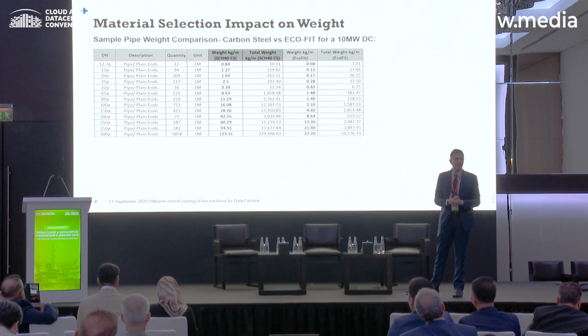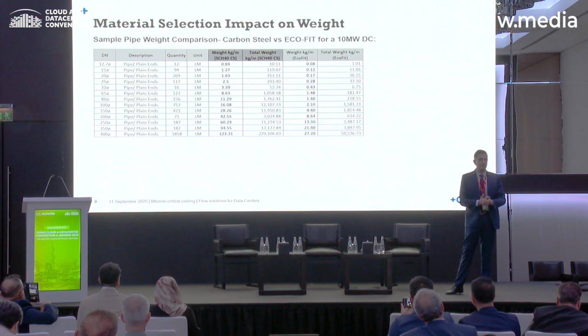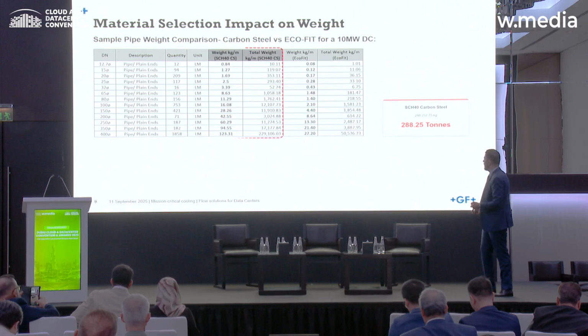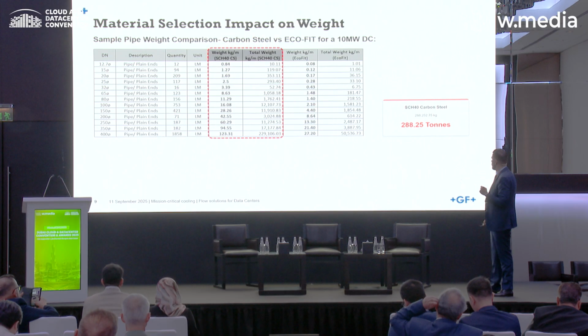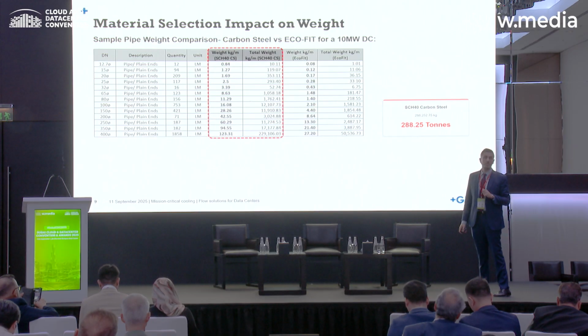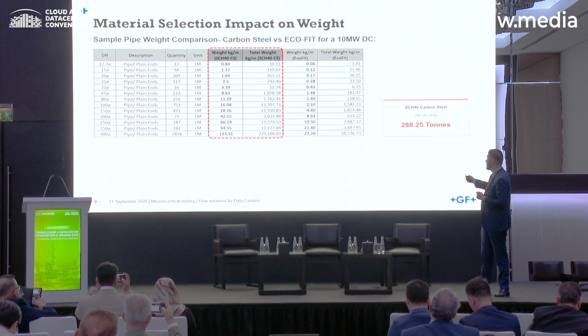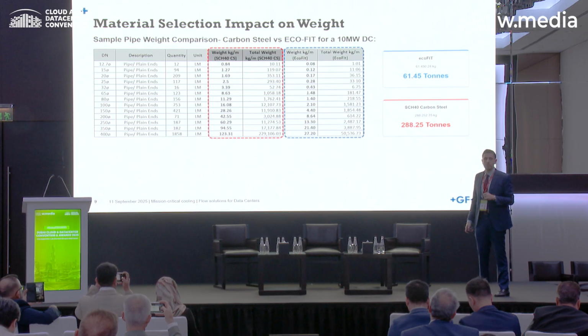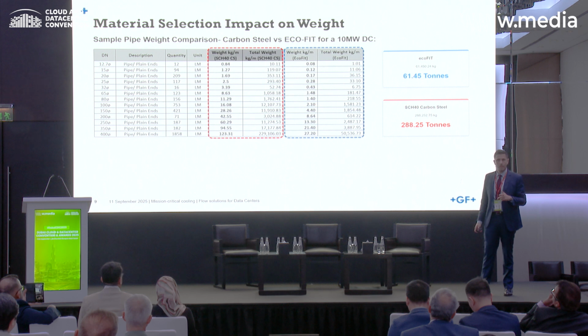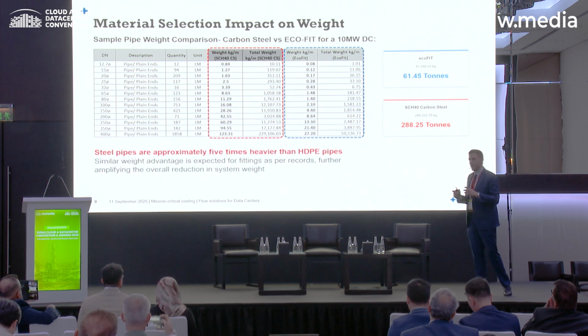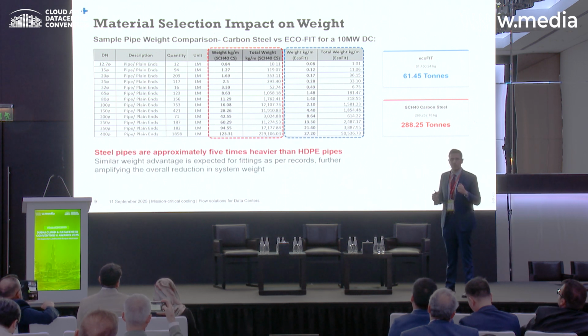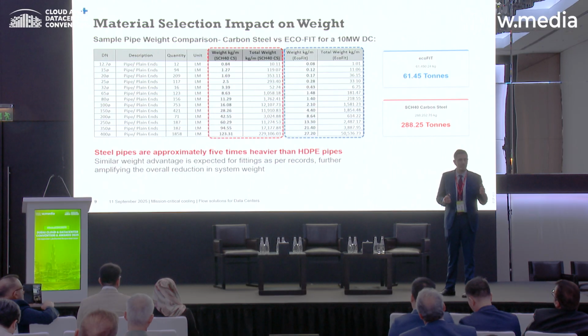The capacity of the data center in our case study is 10 megawatts. The weight of pipes only was found to be 288 tons in carbon steel, whereas with HDPE, this weight reduces to 61 tons. So we're talking about a difference of 5 times, the weight of carbon steel is 5 times that of HDPE.